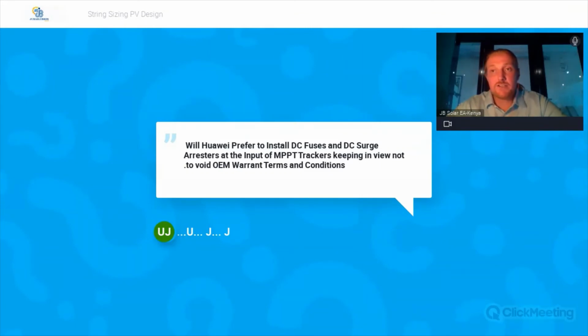So I recommend to my customers to install fuses on the DC side, because in case you have to do some maintenance or if there's a problem, you can remove the fuses first, and then you can work on the inverter, because you should not remove the DC cables from the inverter while there is a current flowing.